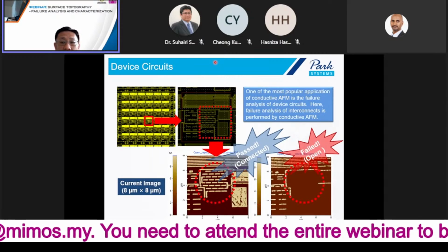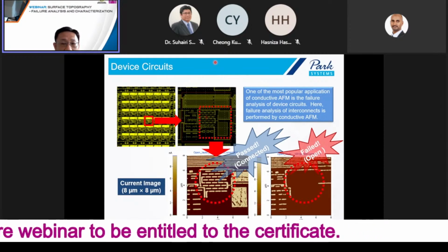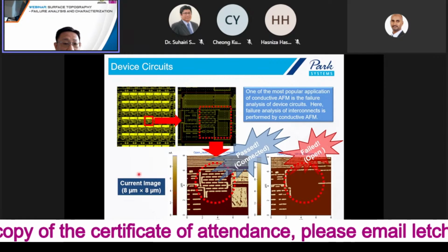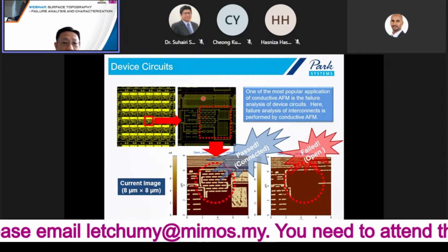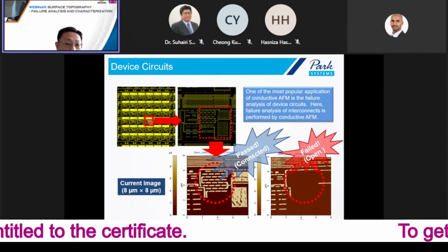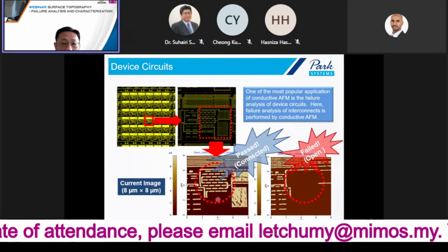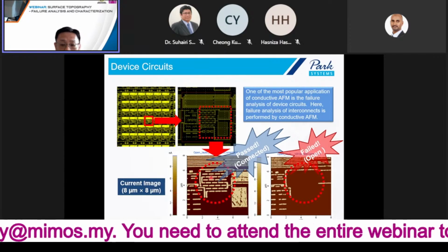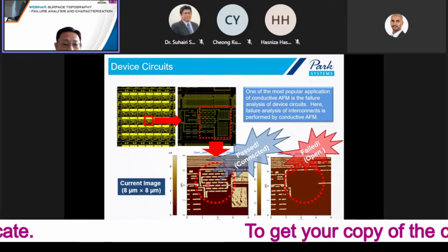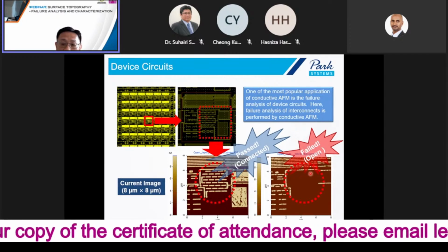So one example is device circuitry. This is a common application for failure analysis. First, these are device circuitry which conduct current. So we are able to get a current image at the same time as the height image. From the height image, we cannot tell whether the circuit is bad or not because it's very small circuitry. However, we can zoom in and do this conductive AFM scan and we can see which areas are conducting. In this case, this circuitry passed because there are conductive areas. However, this circuitry failed because some of the circuits are already open, already gone.